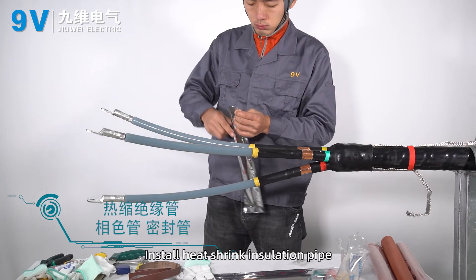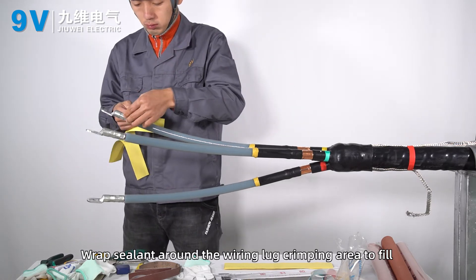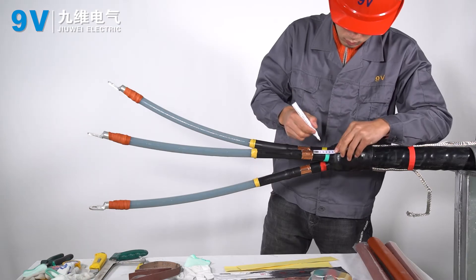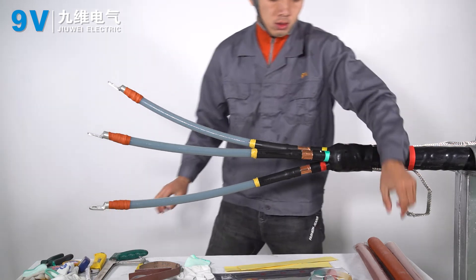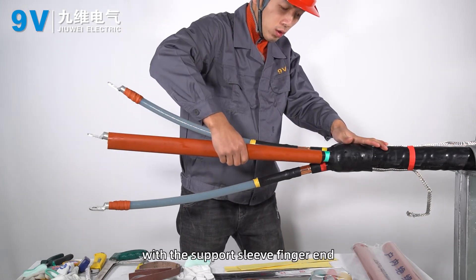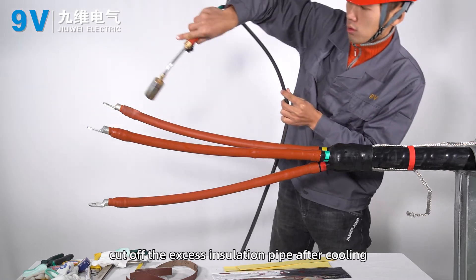Install heat shrink insulation pipe, heat shrink rain skirt, phase collar pipe, and seal pipe. Wrap sealant around the wiring lug crimping area to fill the gap between the insulation layer, the lug, and the lug indentation. Put the insulation tube into the lap of 20 to 30 millimeters with the support sleeve finger end. Heat and shrink evenly from bottom to top. If the insulation pipe is too long, cut off the excess after cooling.